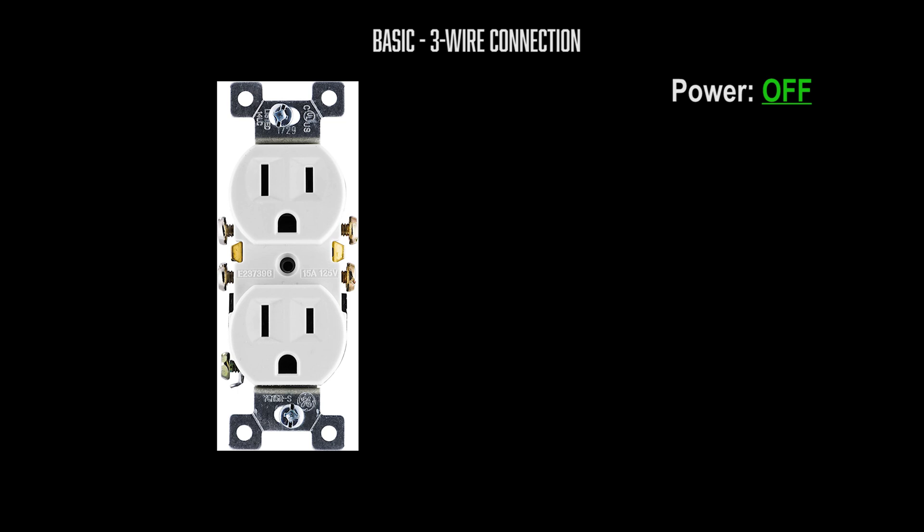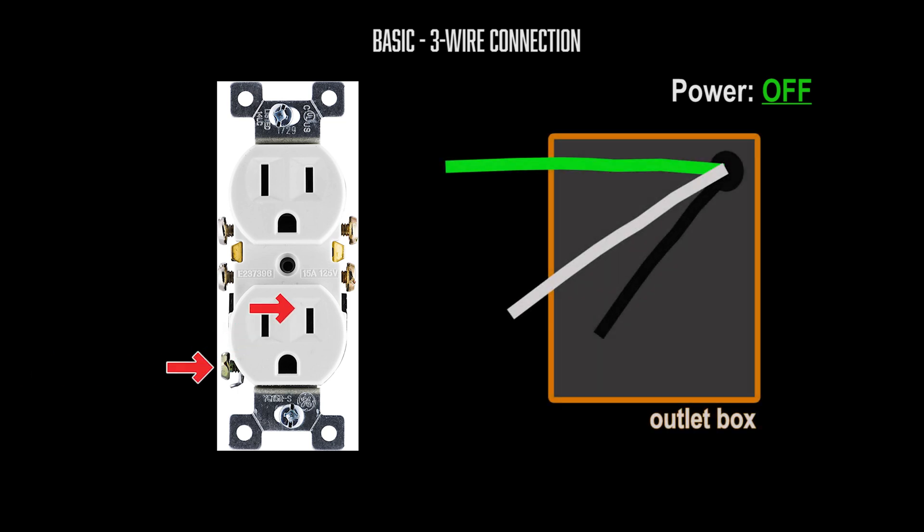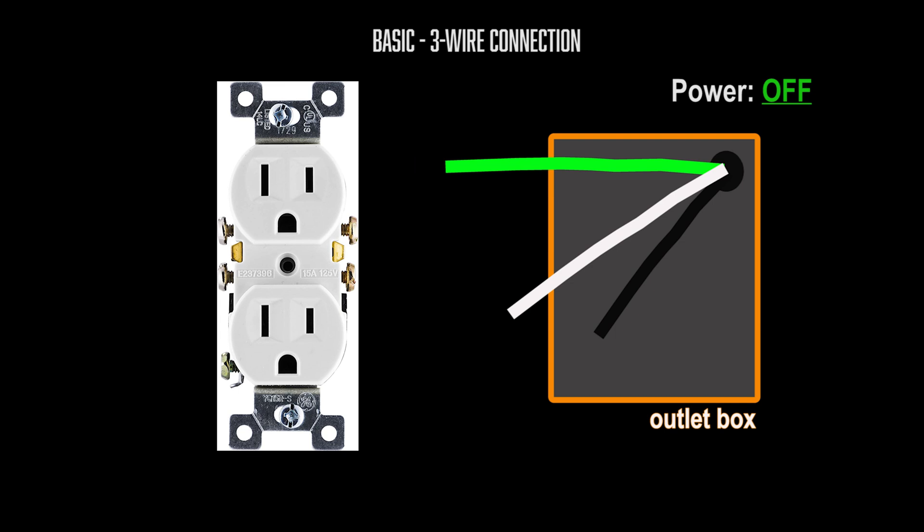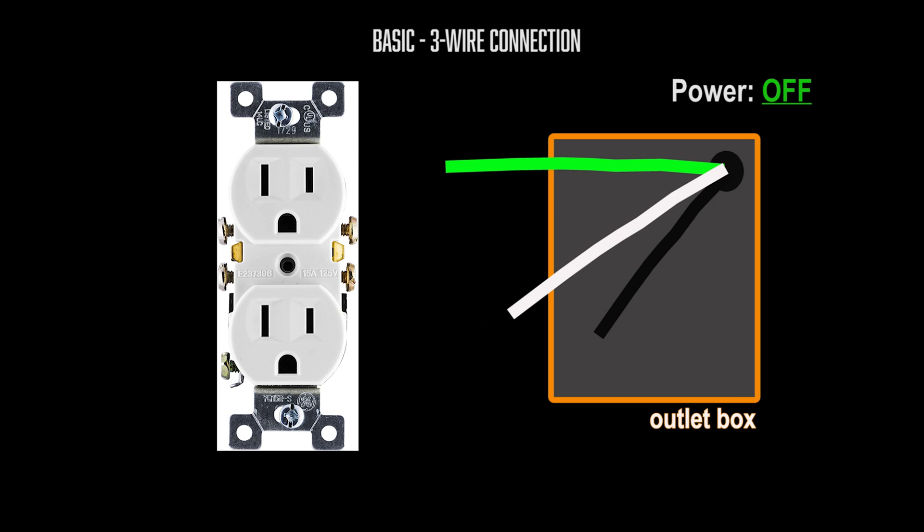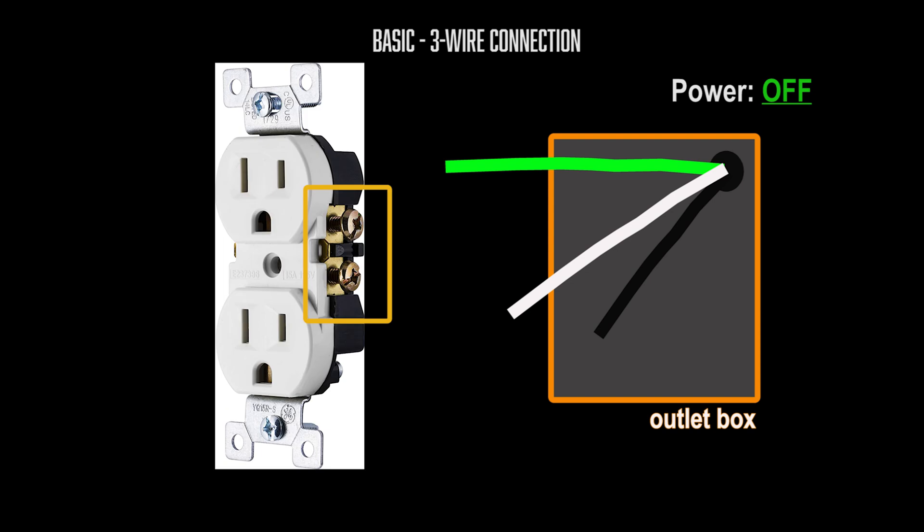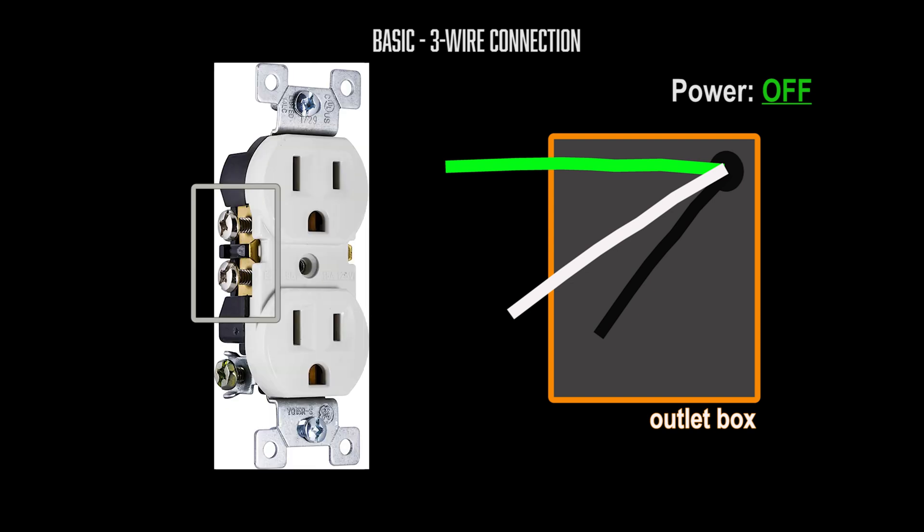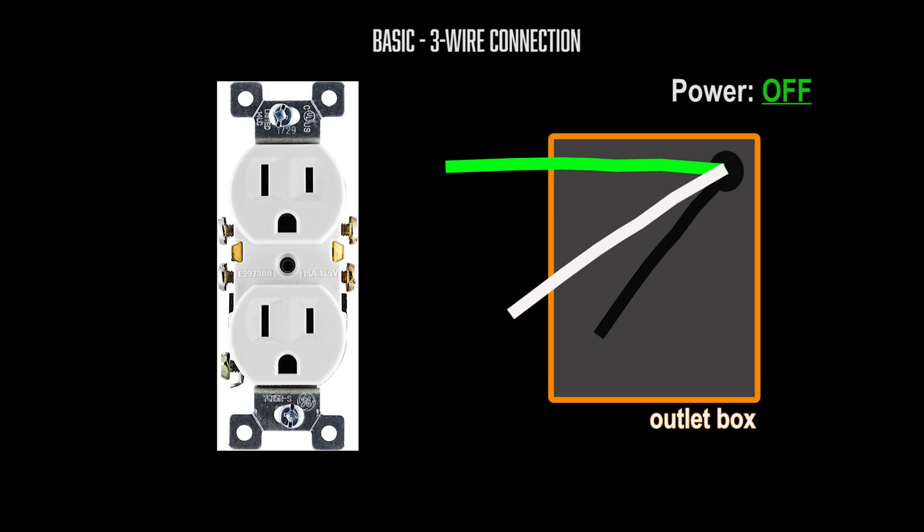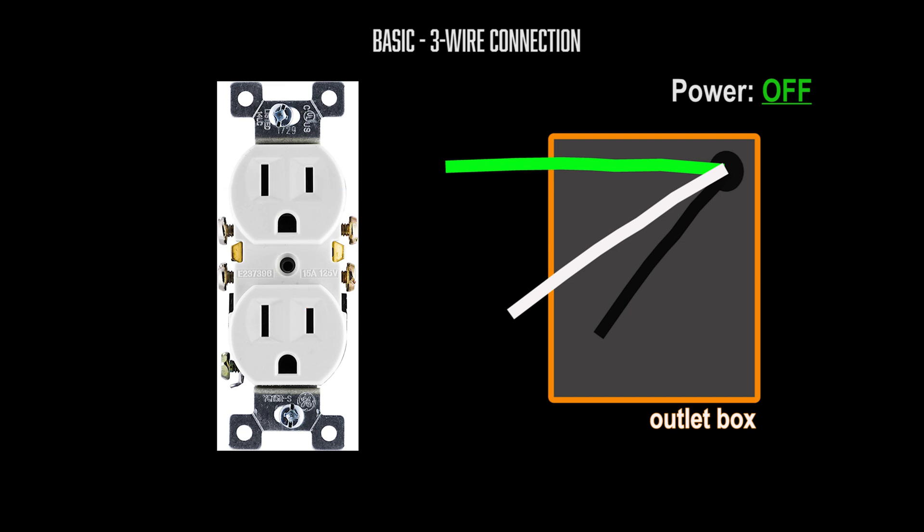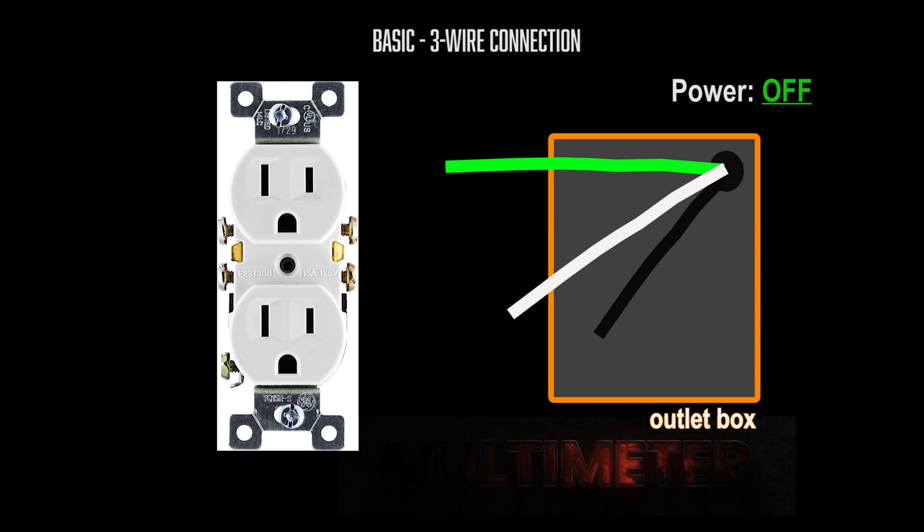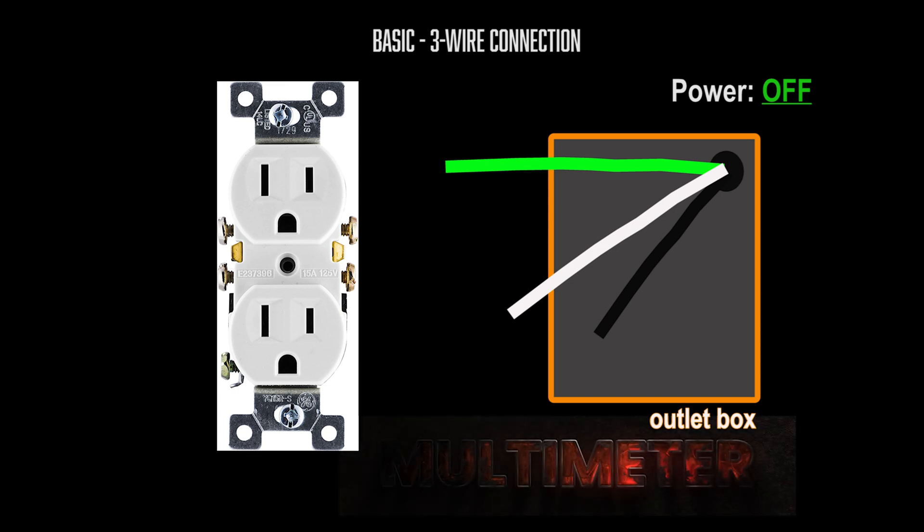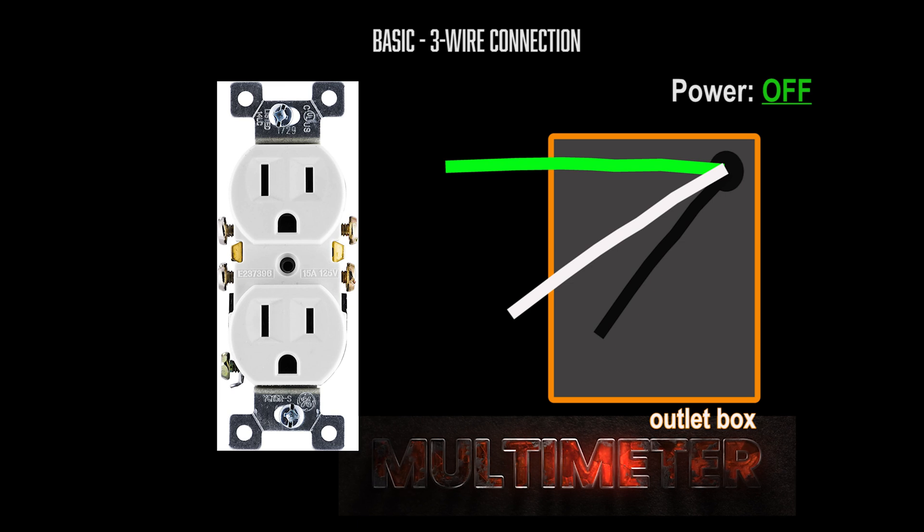First we must find a ground. It should be a green or a copper wire. Quite frequently it is not insulated. Now we must figure out which of the remaining wires is hot and which one is the neutral, returning the power back into the circuit breaker. Brass screw is usually hot and silver one is usually neutral. And hot is usually on the right side and neutral is usually on the left. But then again, you can look at the labels by the screws or rely on the colors of the screws, but you should always double check using a multimeter.